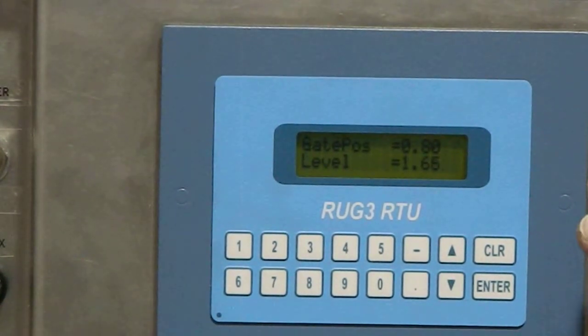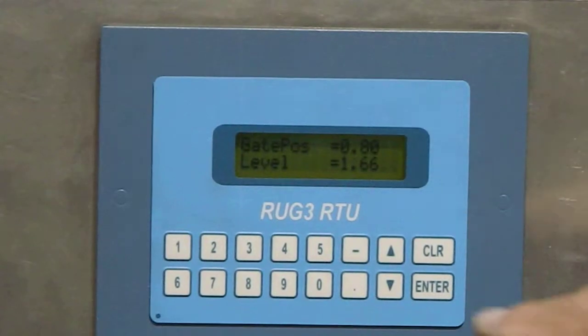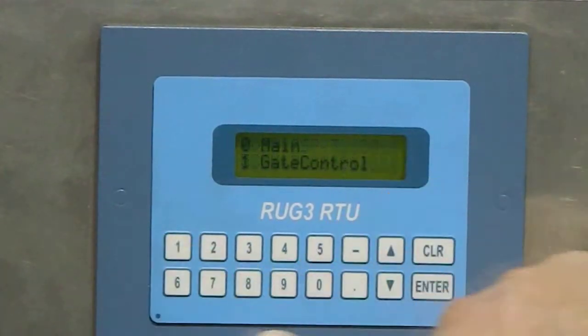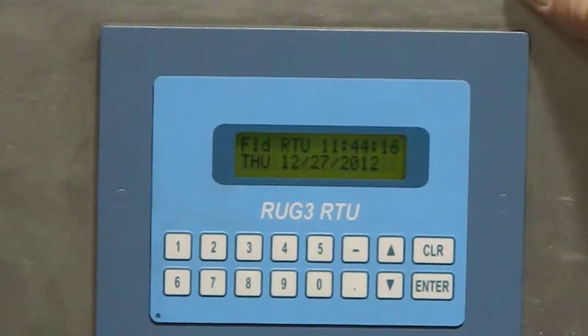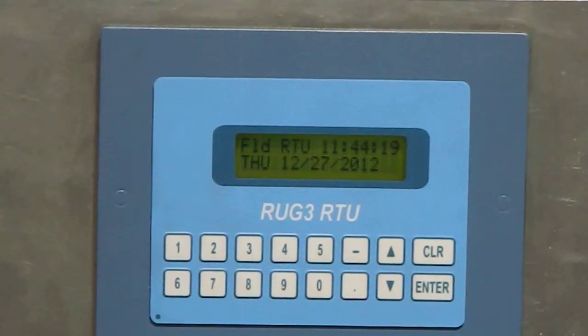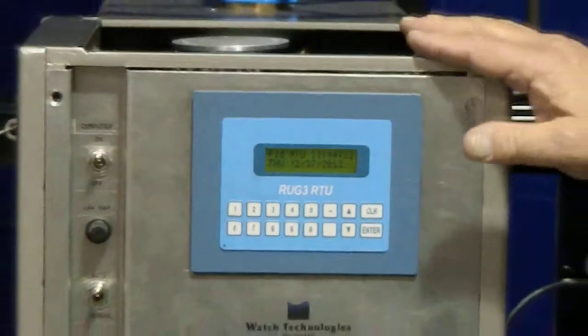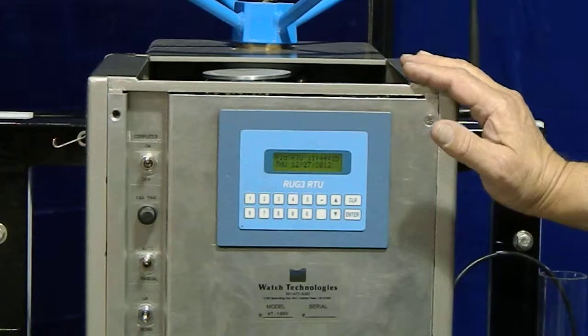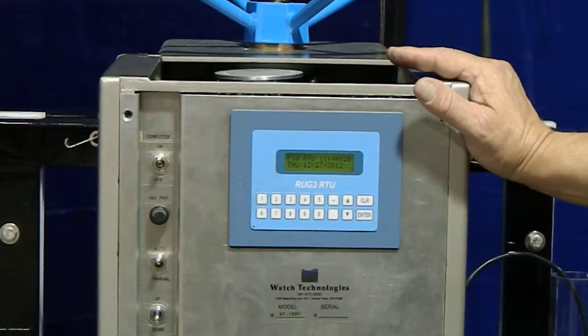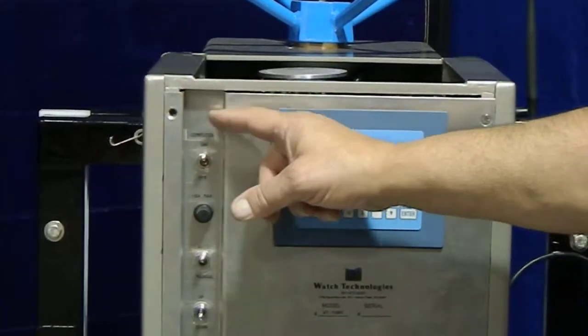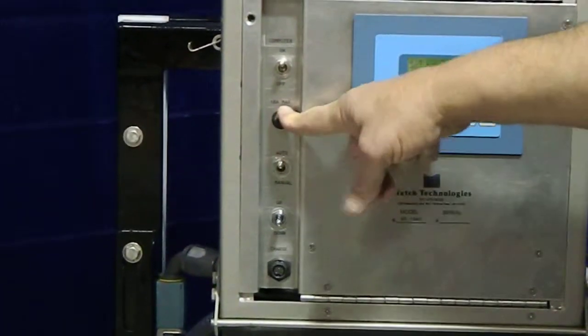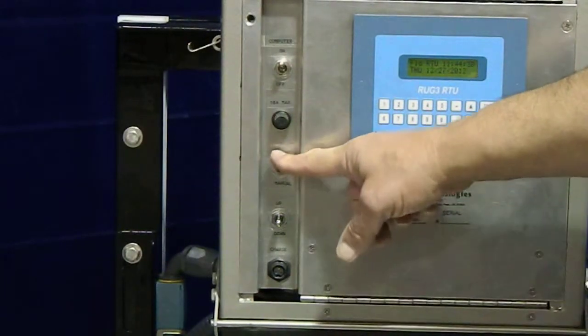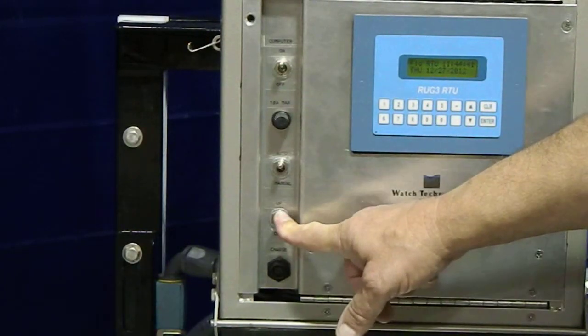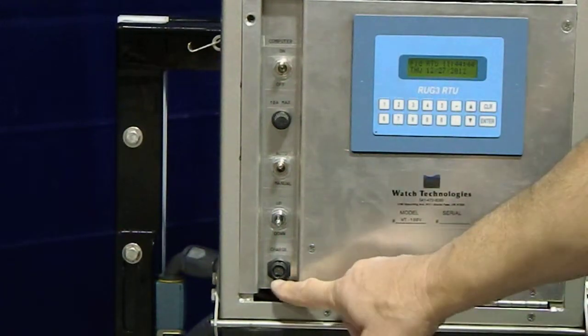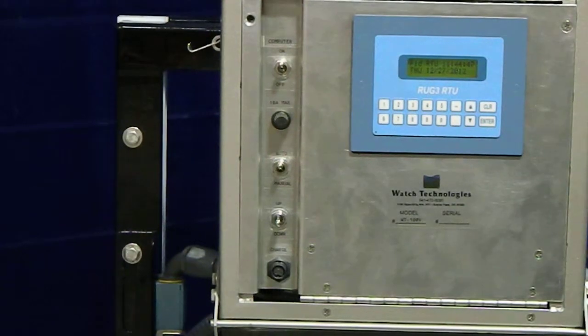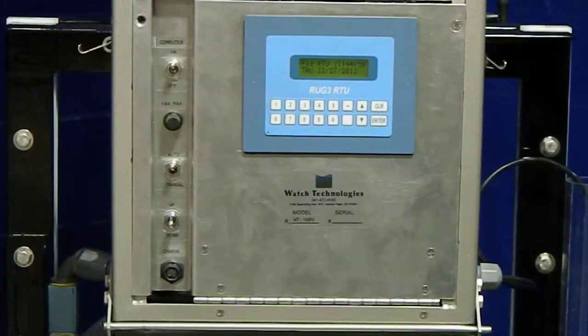Okay, so on the screen on the remote RTU, we also have two screens. Now, I refer to this as an RTU actuator. It's an actuator, which has the motor and the whole system to run the gate, but it also is an RTU embedded within it. So it's actually doing two jobs. It's an RTU and an actuator. And the switchgear on the side is, once again, on and off for the computer. Here's our fuse for the whole system. Our auto manual, up and down momentary, allows you to adjust the gate manually, and there's an external power connector in case for any reason the system doesn't have power. You can attach a battery pack to it and make it operate.